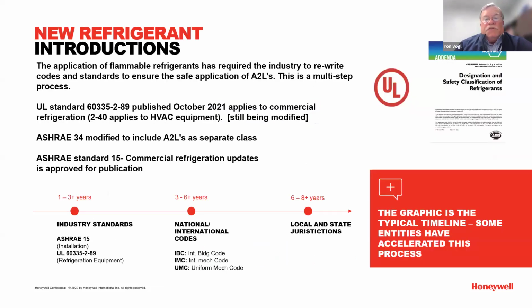Now, when we introduce a refrigerant, the timeline on the bottom is how it used to go. We would develop something based on a reg or something we innovated, and we would take this refrigerant, test it in our labs. Then we would send it to ASHRAE standard 34 to verify what we know about it - non-toxic, non-flammable, all the other characteristics. And then once it was done in ASHRAE 34, if you're going to use it, it would go to ASHRAE standard 15, which is a safety classification for using it in equipment, and they would write regs around it. Then it would find its way to the national and international building codes. You can see the time frame there.